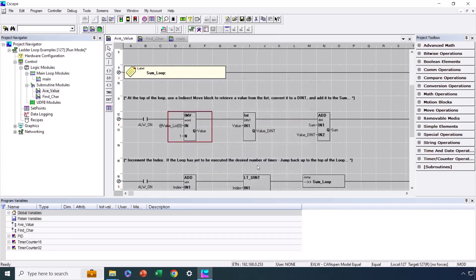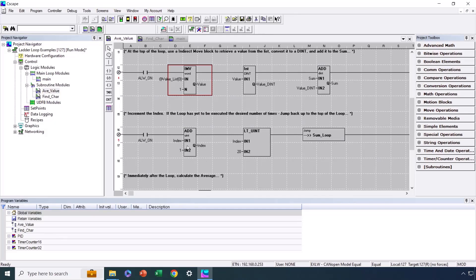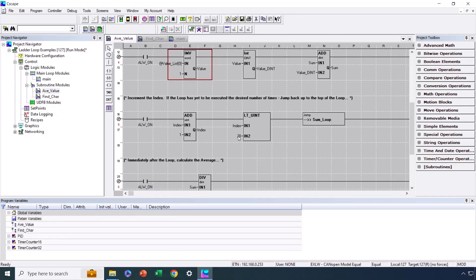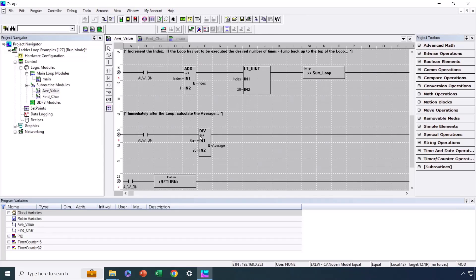Once we have retrieved our value, we convert it to a double integer to accommodate a large result from the sum of the 20 members of our value list, which helps us avoid overflow issues. The sum value starts at 0 when it first goes through the loop and builds on itself each time. Next, we increment our index and then test it to make sure we have gone through the loop less than 20 times, as our index will range from 0 to 19. As long as we are at less than 20, we execute our jump function, which brings us back into the loop. Once our index reaches 20, our condition will be false and we will drop out of the loop. We then take our sum double integer and divide it by 20 to get our average, and return from our subroutine back into our main routine.